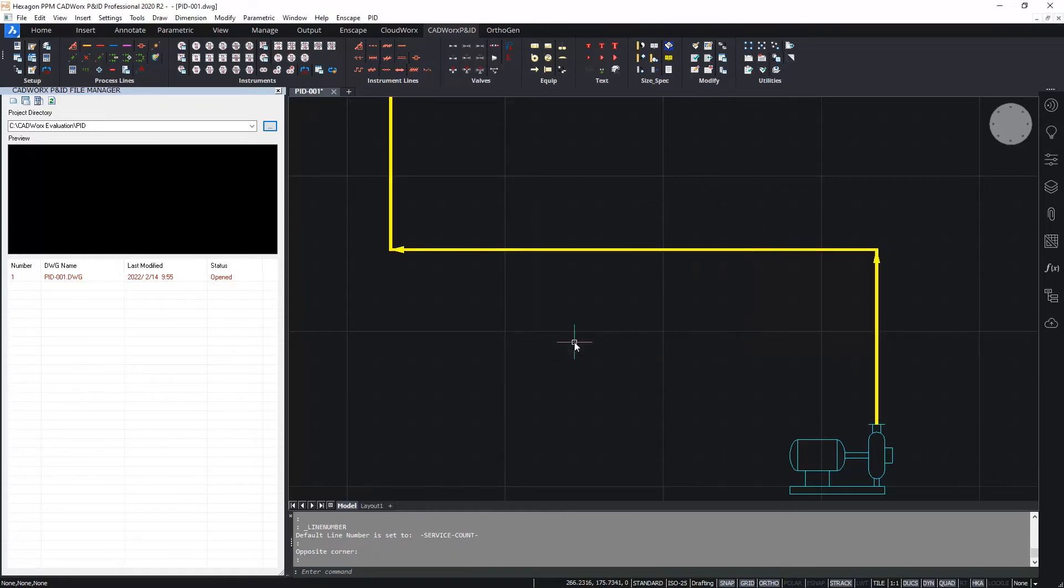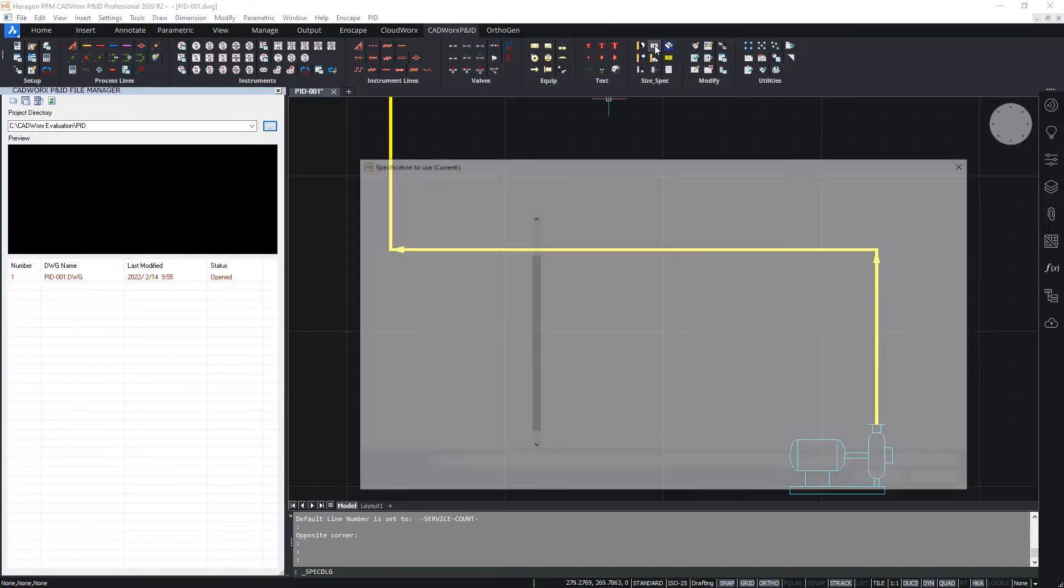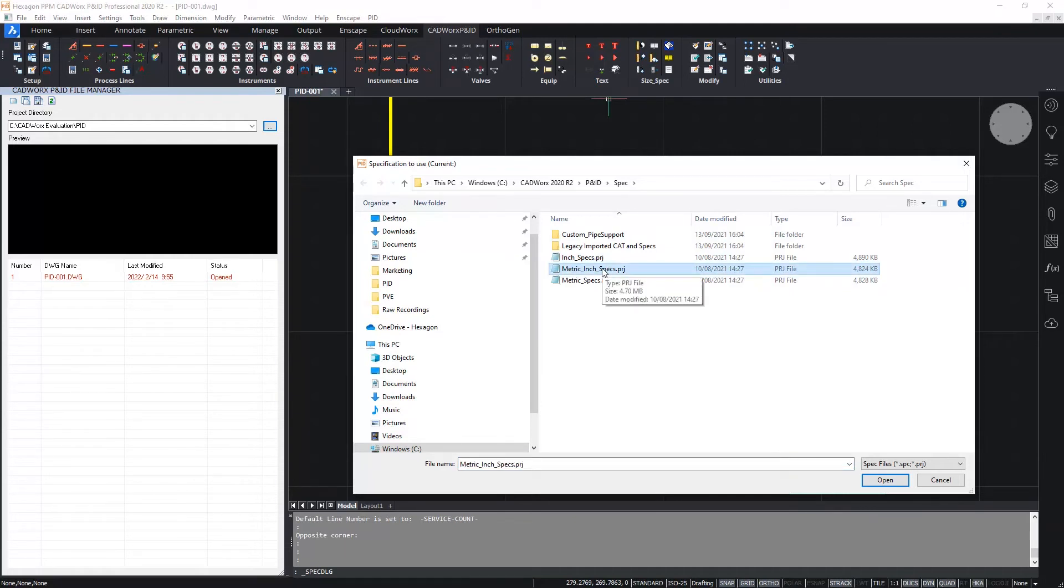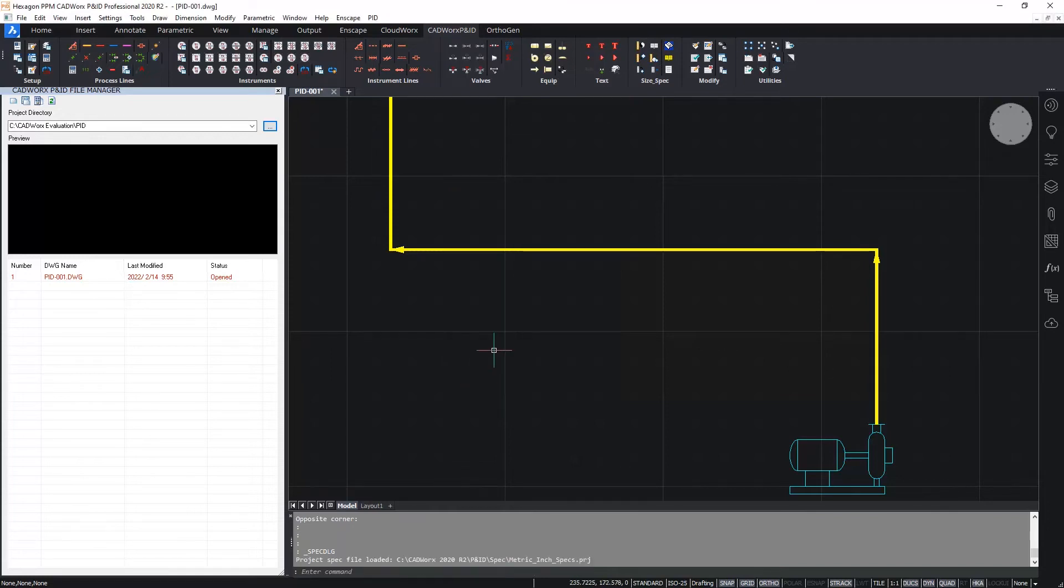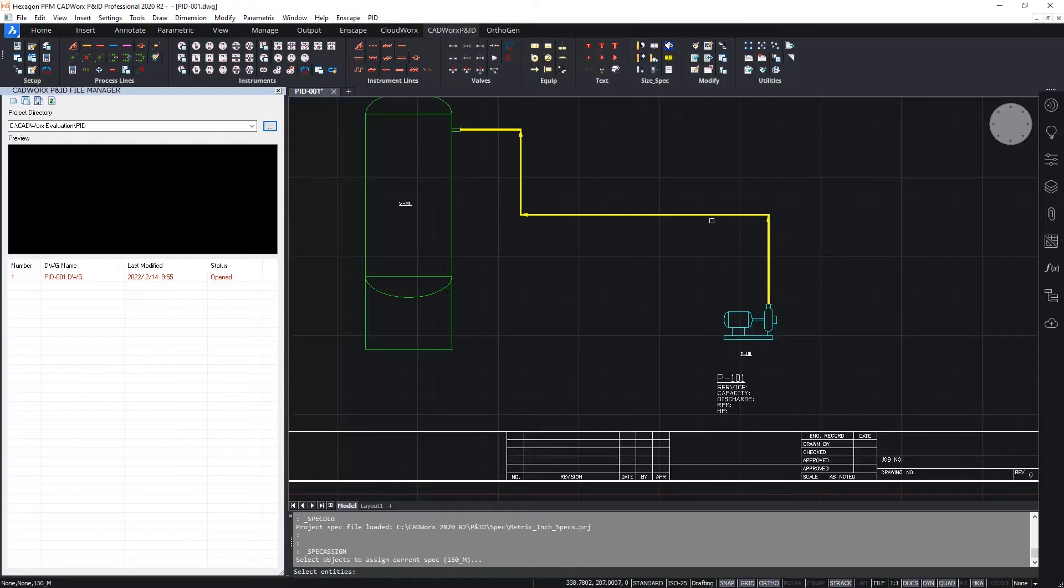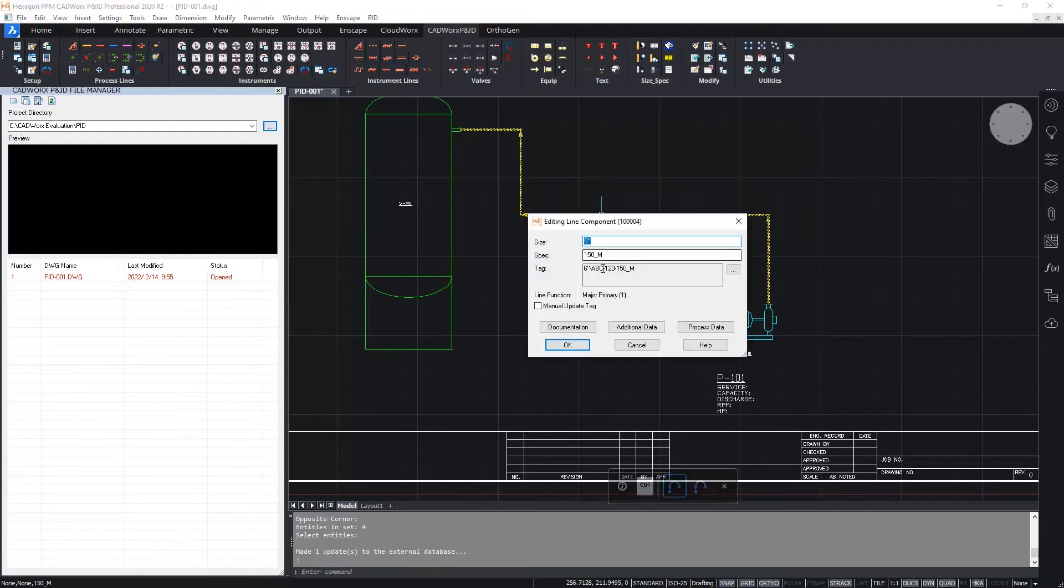For the spec, I'm going to pick that from the specification project. I'm going to go to the size spec section of the ribbon and load up a specification. I'm going to pick from the out of the box supplied specifications, the standard metric inch specification project file. And from within here, I'm going to pick the ANSI class 150 metric inch specification, 150M. Now once that spec is set, I can then assign that to a selection of components. Of course I only have the process line, but I'm going to assign that spec to the entire process line. Now when I double click, we can see the spec has been assigned. The line number, the tag has been completed.